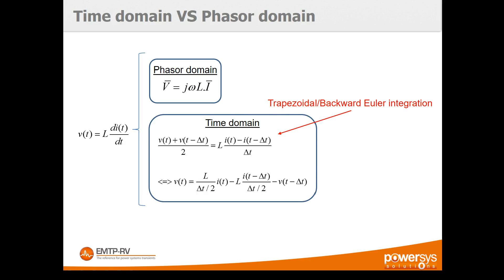In the time domain EMT-type software, we use trapezoidal integration to solve the differential equation. In EMTP specifically, we use both trapezoidal and backward Euler integration to ensure stability. With this equation we can isolate the voltage at a certain time as a function of current and historical terms, and solve the network using nodal analysis — or in EMTP's case, the modified augmented nodal analysis technique.